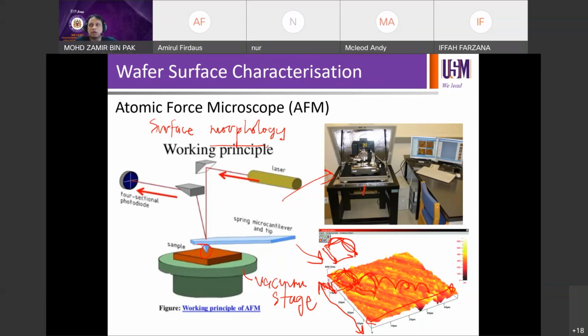On the other hand, if you are looking for features in the range of 300 nanometers, perhaps, then 50 by 50 micron squared would be too big. Okay, so in that case, you might just want to go for 10 by 10 micron. So that will be sufficient already to capture to understand the properties of the sample, having features of about 300, 400 nanometers. Okay, so it really depends on what do you want to see. So you have to know pretty much what you're expecting to see. Unless kalau you tak ada idea of what will you see on the sample, then you'll just scan anyway and see what you get, and then in the second scan onwards, then only you can tune your field size accordingly, or the scan size. Okay, we call this a scan size or field size.